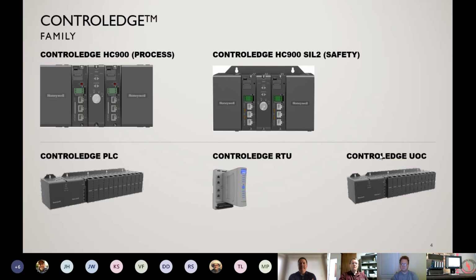In the lower right-hand side, we have the ControlEdge UOC. This is for applications where customers might typically have a large DCS Honeywell system like an Experion PKS or an Experion LX, where you want to add a simple process PLC type rack out into the plant and allow that to live and breathe in the same environment as an Experion programming system. It shares all the same points. It migrates very easily when you're adding points that you add them in the same environment as the Experion PKS system. So this is for the larger DCS systems, typically oil refineries, petrochem, maybe even typically pharmaceuticals, and those type of applications. So this summarizes the ControlEdge family and consists of several different products.